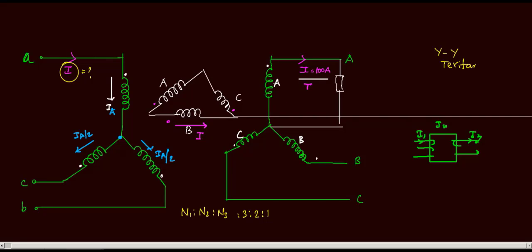This is I2 current, this is I1 primary current. I have a secondary current in phase A, and a reflecting primary current in phase B, dividing this primary current I1 by 2. To compensate this, I have an I3 current in the tertiary winding, because for balancing this I need MMF balance. Here current leaving the dot should have current entering the dot, so I have to place the dot here such that current enters the dot.